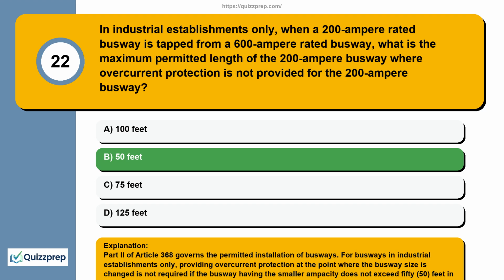Part 2 of Article 368 governs the permitted installation of busways. For busways in industrial establishments only, providing overcurrent protection at the point where the busway size is changed is not required if the busway having the smaller ampacity does not exceed 50 feet in length and has an ampacity of at least 1/3 the rating of the overcurrent protection of the larger busway. 1/3 of 600 amperes equals 200 amperes. Reference Section 368.17(B), exception.